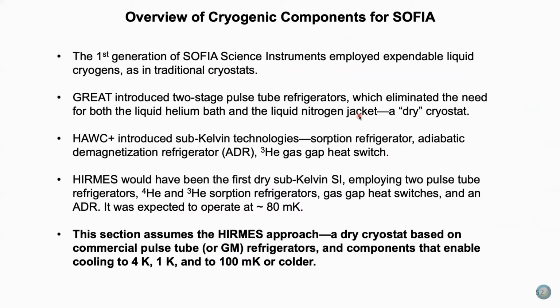So the first generation of SOFIA science instruments employed expendable liquid cryogens - they were wet cryostats. GREAT introduced the two-stage pulse tube refrigerator, which meant that it was a dry cryostat. It used no liquid nitrogen or liquid helium.